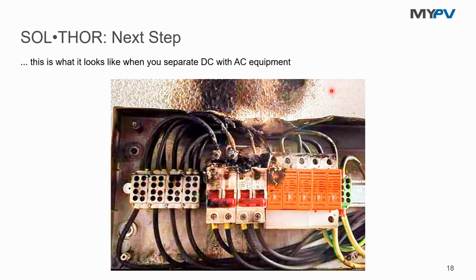All right, I think you've solved all the problems there. That's pretty cool. So that's what can happen when you switch off DC connections by AC switches. That's not what we want to have. We've had plenty of problems in Australia with failure of even DC switches on roofs because of lots of factors. So DC is very challenging when it comes to switching. It's a clever approach to pulse the DC so that it's easy to switch, since it's going through 0 volts.